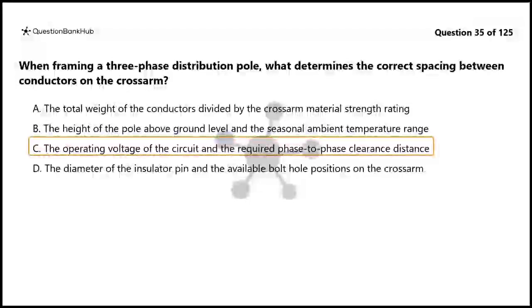The correct answer is C. The operating voltage of the circuit determines the required phase-to-phase clearance, which dictates conductor spacing on the crossarm. Higher voltages require greater separation to prevent flashover between phases under adverse conditions such as wind, ice loading, and contamination. Standard crossarm configurations specify pin positions that maintain adequate clearances for the design voltage while accommodating the mechanical loads.